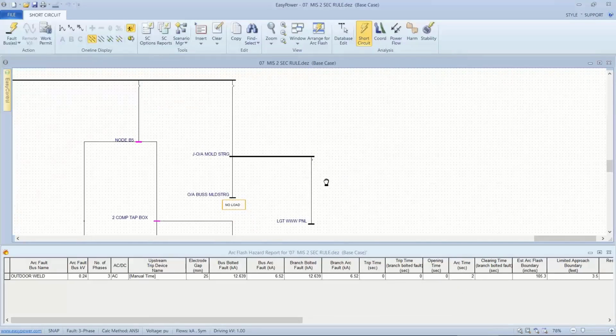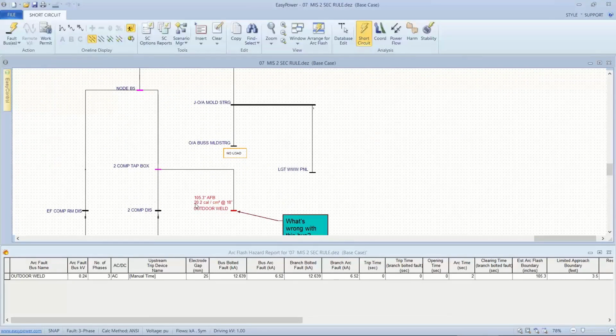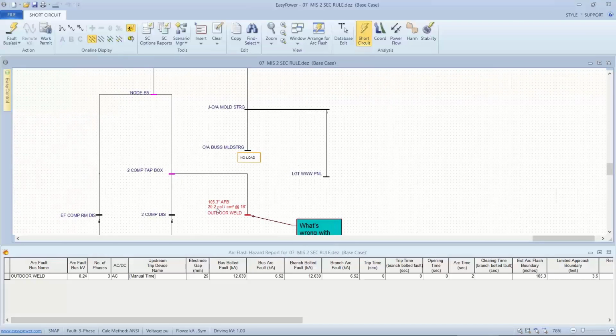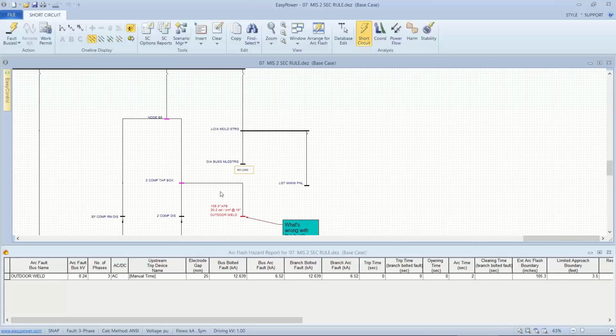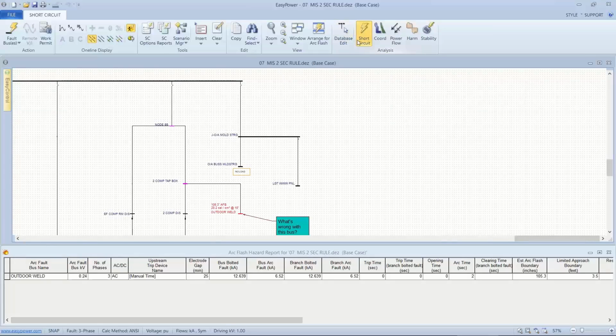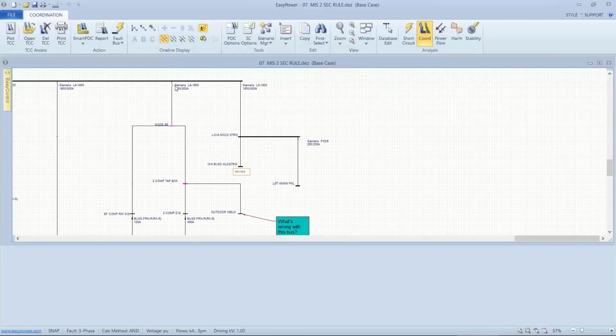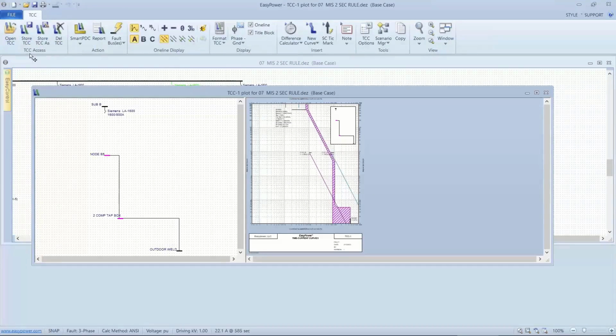Now when I come back to this, my results went down. They improved slightly, but it's still indicating a dangerous level of incident energy. So this backs the question up, what's the trip device doing? Why isn't this being protected by the system? So if I spread out a little bit and go to coordination, select the breaker and a couple cables and this outdoor weld panel and plot the TCC, it becomes apparent what's going on.